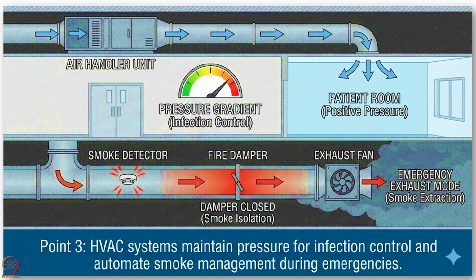This figure shows the HVAC system maintaining pressure for infection control and automating smoke management during emergencies. You can see the air handler unit and the pressure gradient shown for infection control, where the patient room is under positive pressure. A smoke detector triggers fire damper closure and smoke isolation, with an exhaust fan turning on in emergency exhaust mode to extract smoke. Proper HVAC installation is very important in dealing with emergencies.